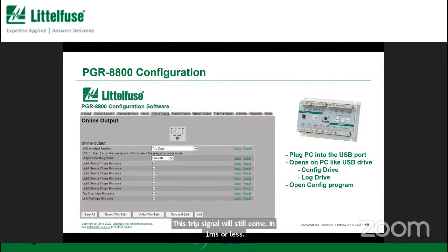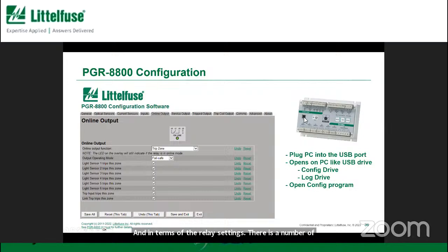And in terms of the relay settings, there's a number of settings that can be made, and it's configured by plugging the USB into a computer. And the software does not need to be installed ahead of time. You simply plug it into the computer, it opens up like a USB drive, and you open the configuration tool. So it's very simple. There's nothing you have to install on the PC.